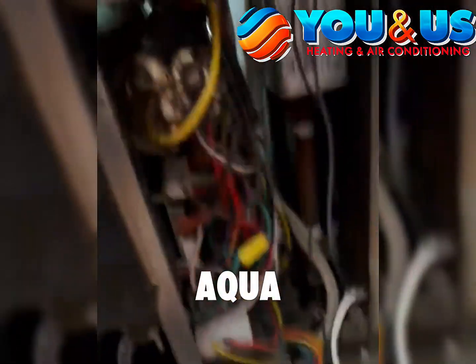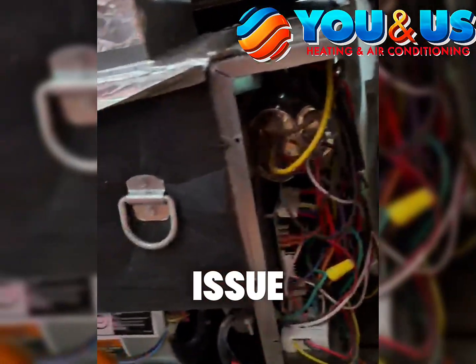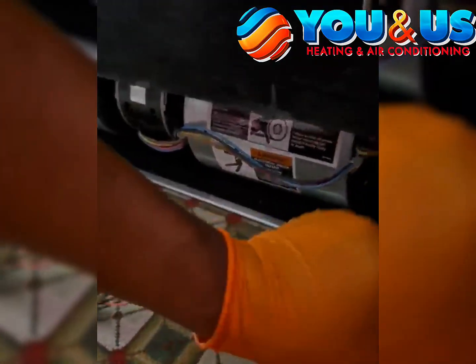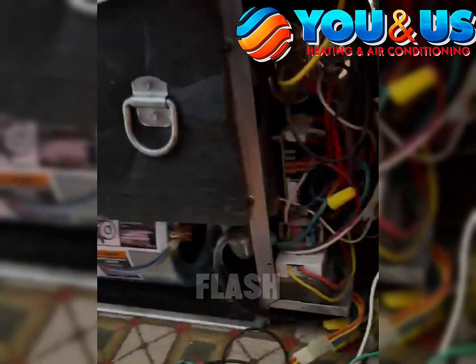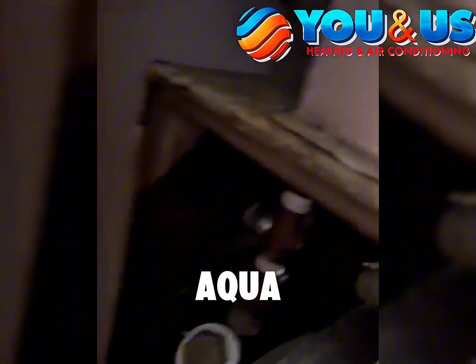It is an Aquastat issue. The orange and the blue wire is for the Aquastat. So the reason why we're having that 9 flash and preventing the AC from running is because this Aquastat right here is dead. Okay.